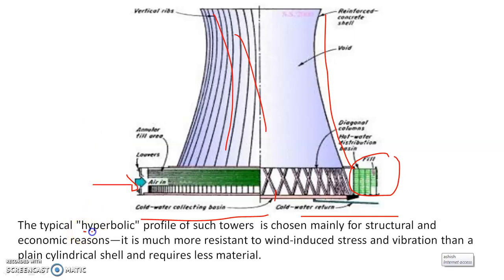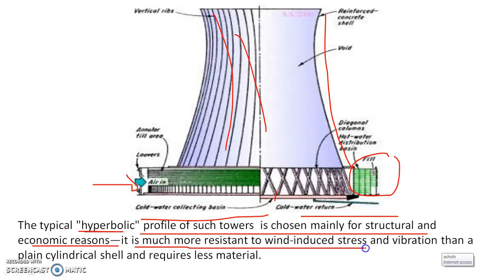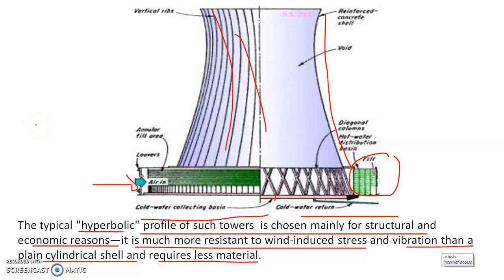The typical hyperbolic profile of such a tower is chosen mainly for structural and economic reasons. It is much more resistant to wind-induced stresses and vibration than a plain cylindrical shell, and requires less material. This is why the hyperbolic form is used rather than a parabola or other shape.